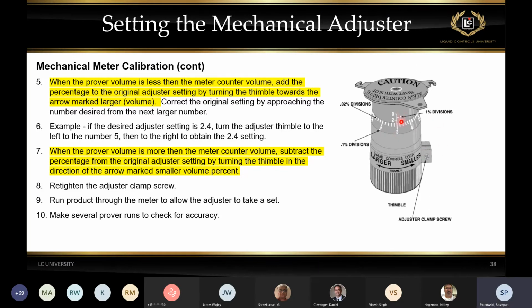The only comment I would make here is that anytime you go down in a scale, you want to go past the set point. So if we want to set it at 2.8, we want to go past that point and then come back to 2.8. Again, it is important because of the design of the adjuster that you go past the point and come back to it. If we look at a second scenario, when a prover volume is more than a counter, now we want to speed up that counter so it turns faster to indicate what's being delivered to the prover. In this case, we would subtract percentage error from the adjuster setting and turn that adjuster up towards 0.